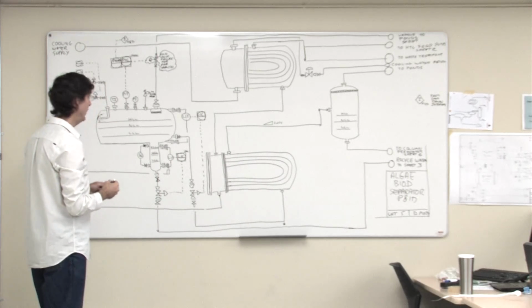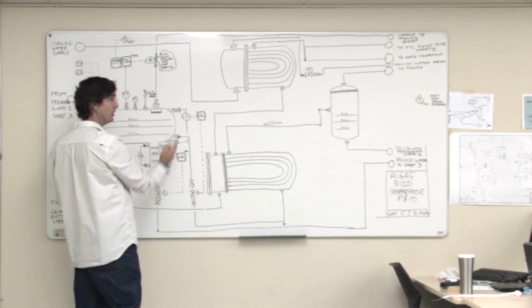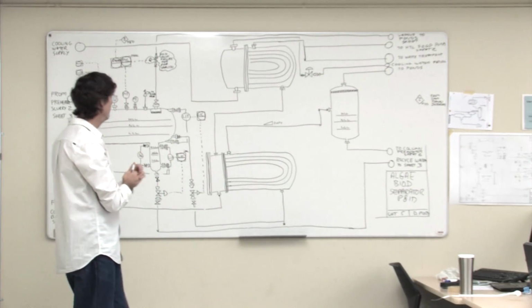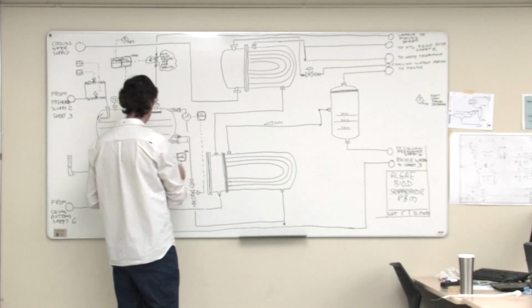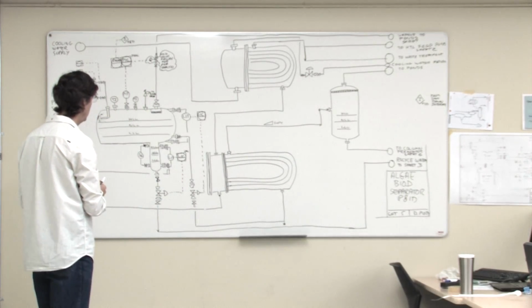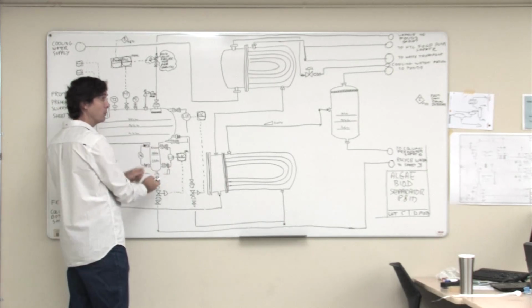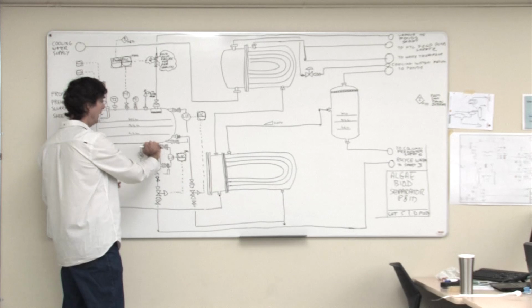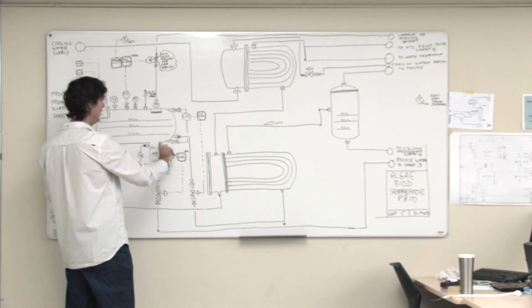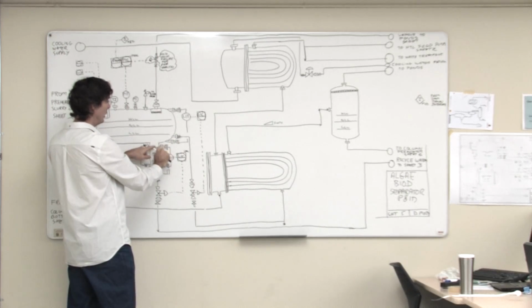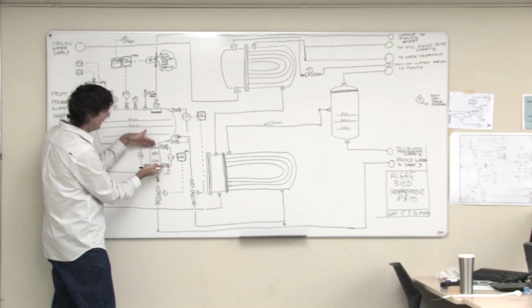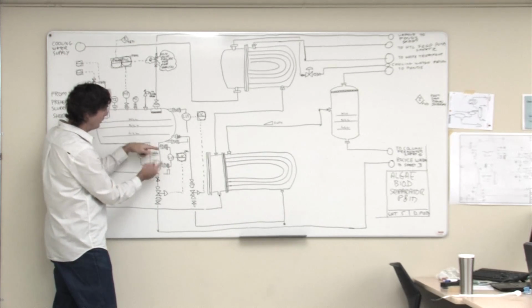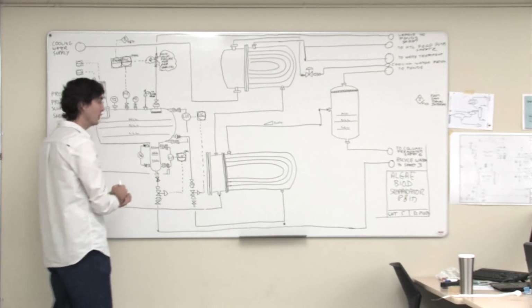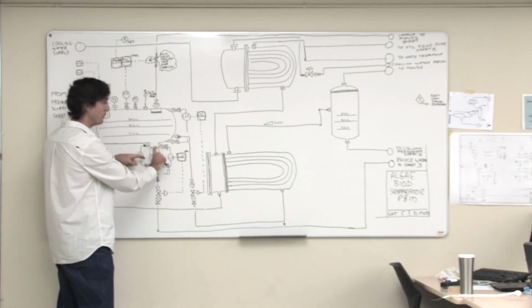And because we're thinking it's going to be dirty, we're going to put seals on as well. Could the level at the bottom, like the water, also be measured by differential pressure? Yeah, this is still differential pressure. You're measuring basically the pressure of the oil. As this level goes up and down, the pressure up here moves with it, and that gets compensated for by measuring that pressure. So you get a fairly true measurement of where the level is down here in the boot.